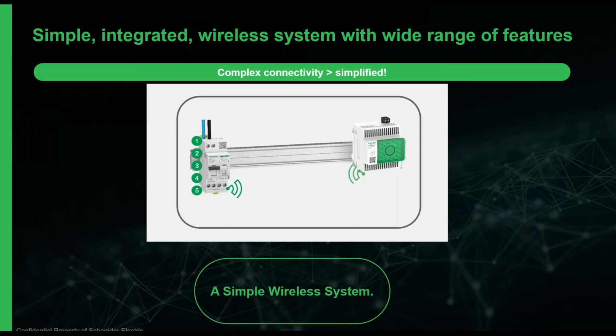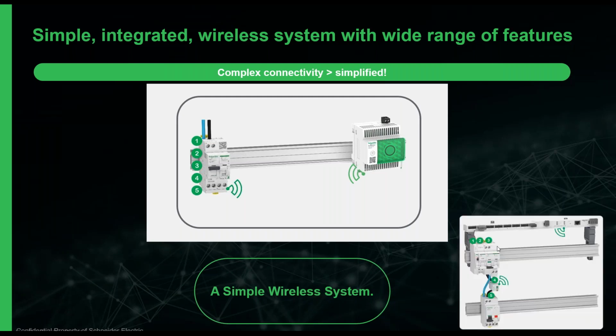We bring all of that into one device. That itself is a significant advance in technology. So the system is very much a simplified and integrated wireless system with a wide range of features. You would have thought it would have become a complex connected solution, but it's not. It's very much simplified. The bottom right image shows the multiple devices that would have been required if we were to use traditional devices and technologies to try and build this sort of system together. We would have had an arc fault detection device, a power tag device, an auxiliary, an overvoltage release, an RCD or an RCBO, connected wired to a smart link bar, then going out to the network. But we've done away with all that. We've integrated this into one single device with all of that feature set.